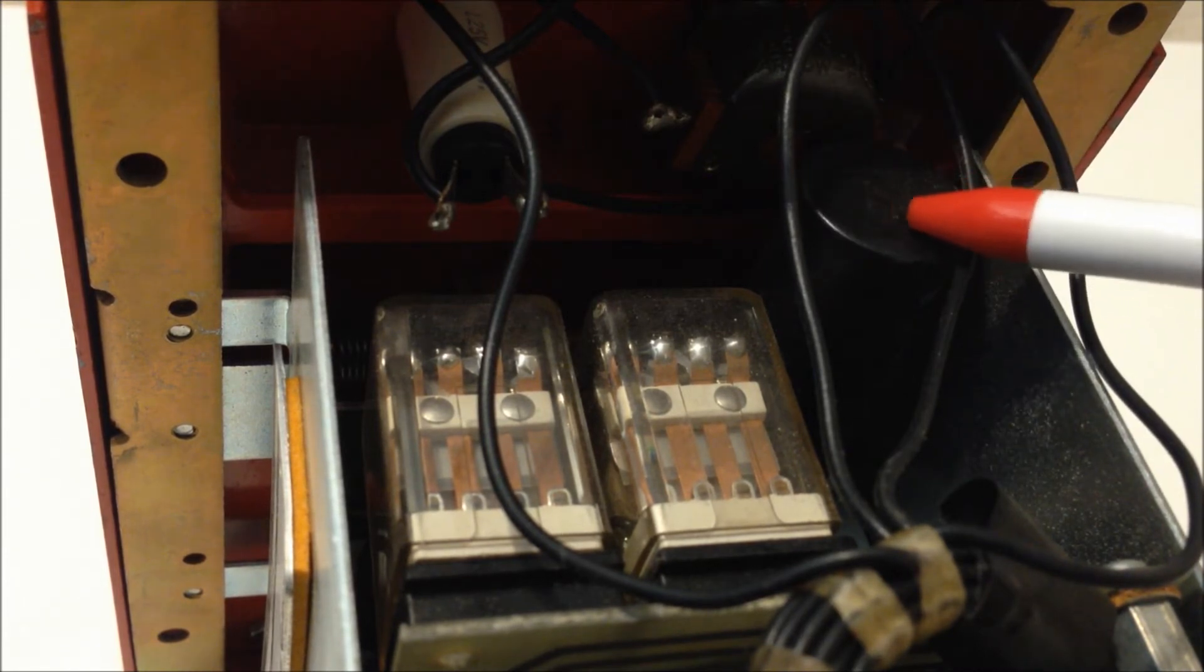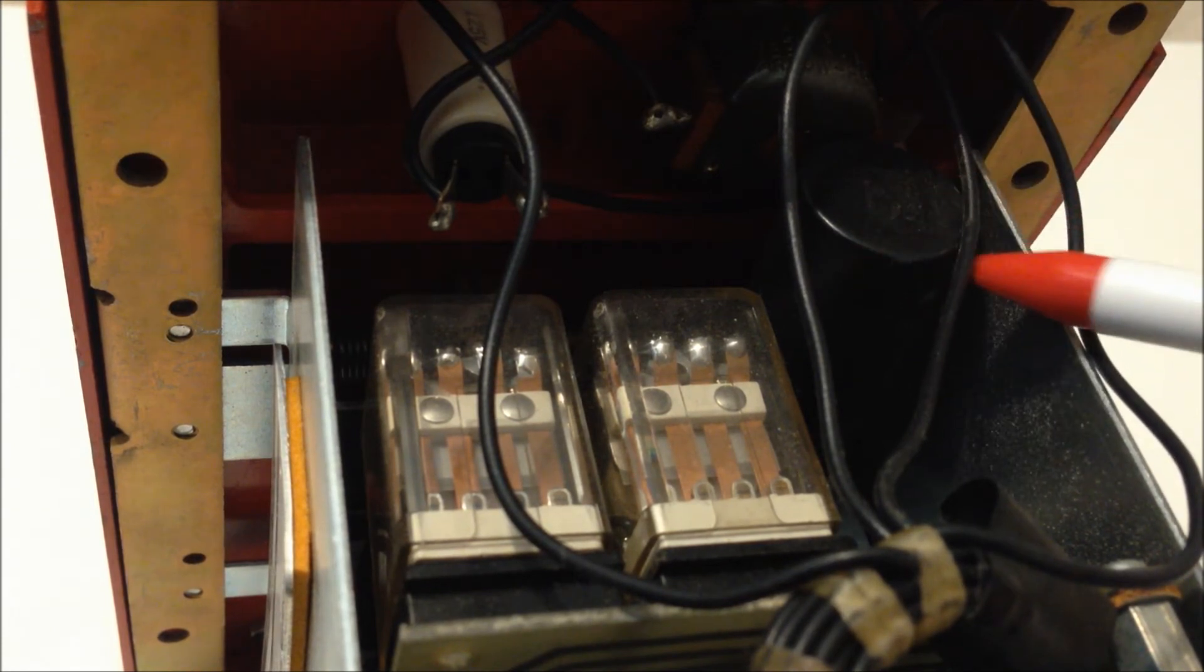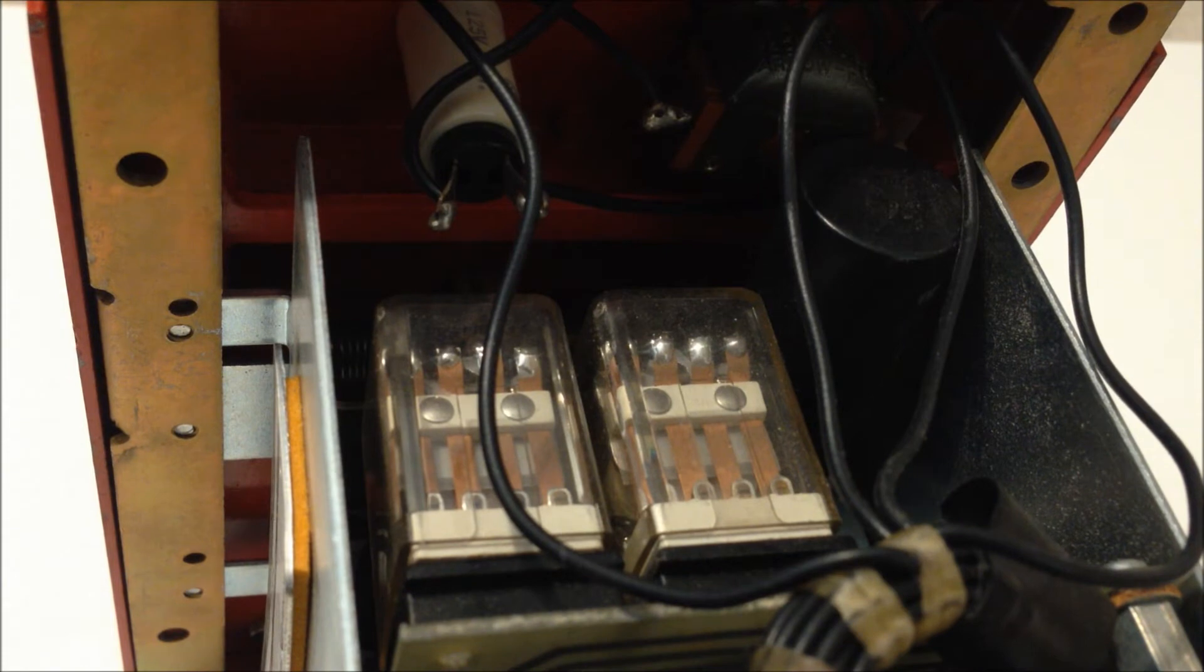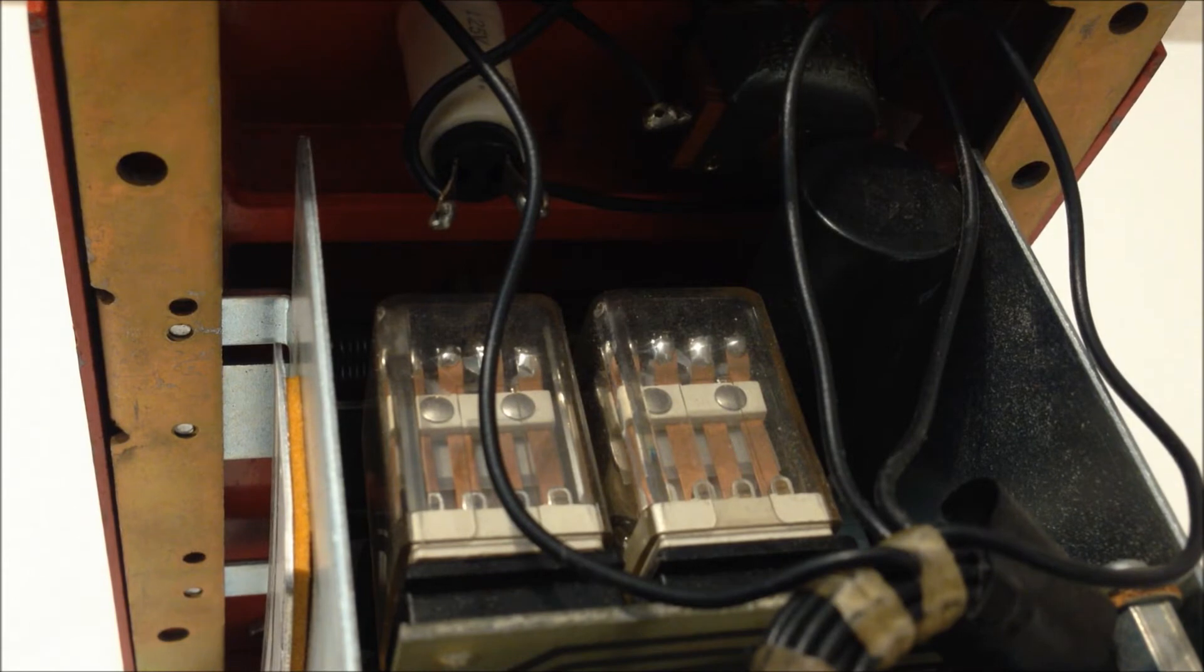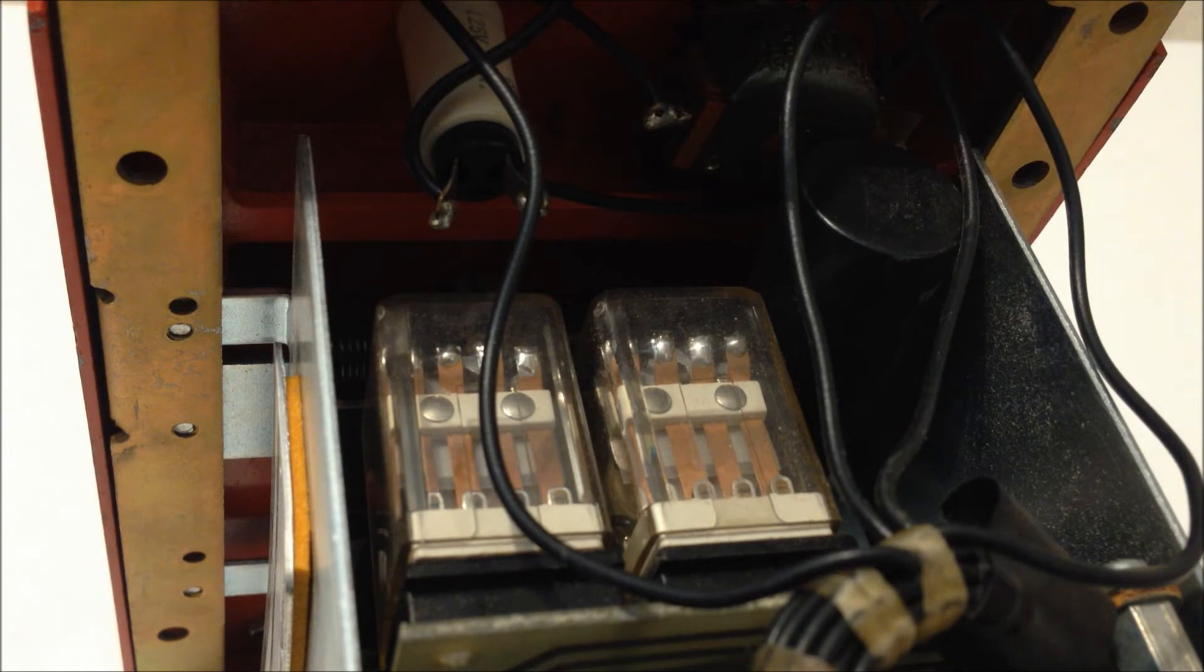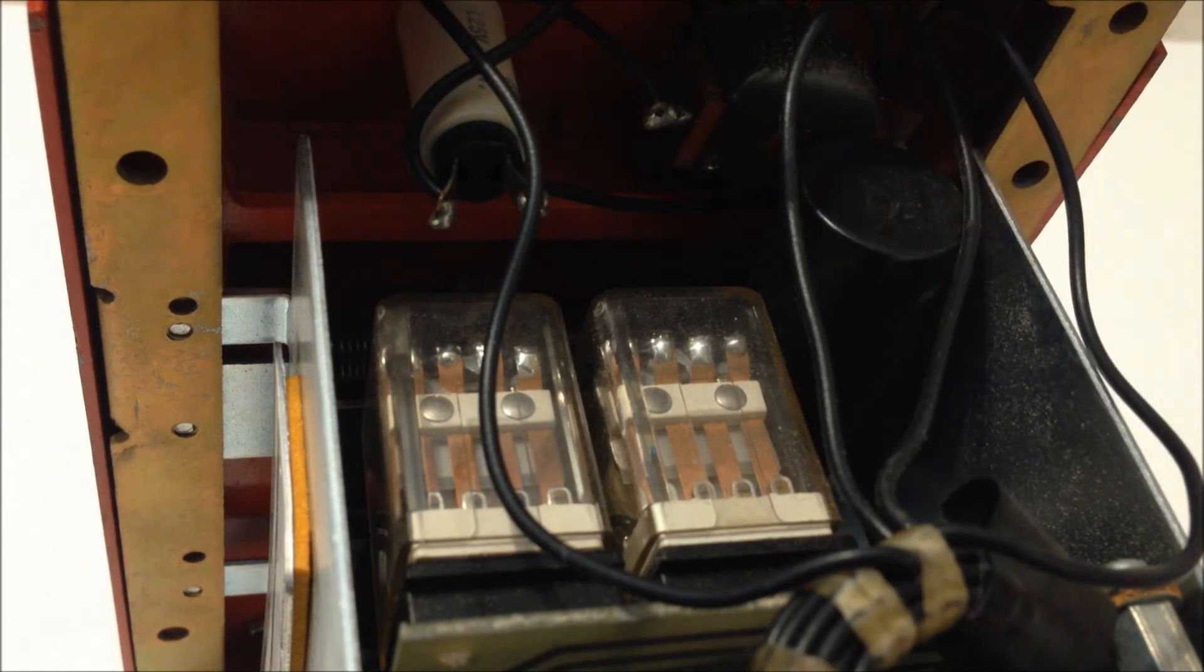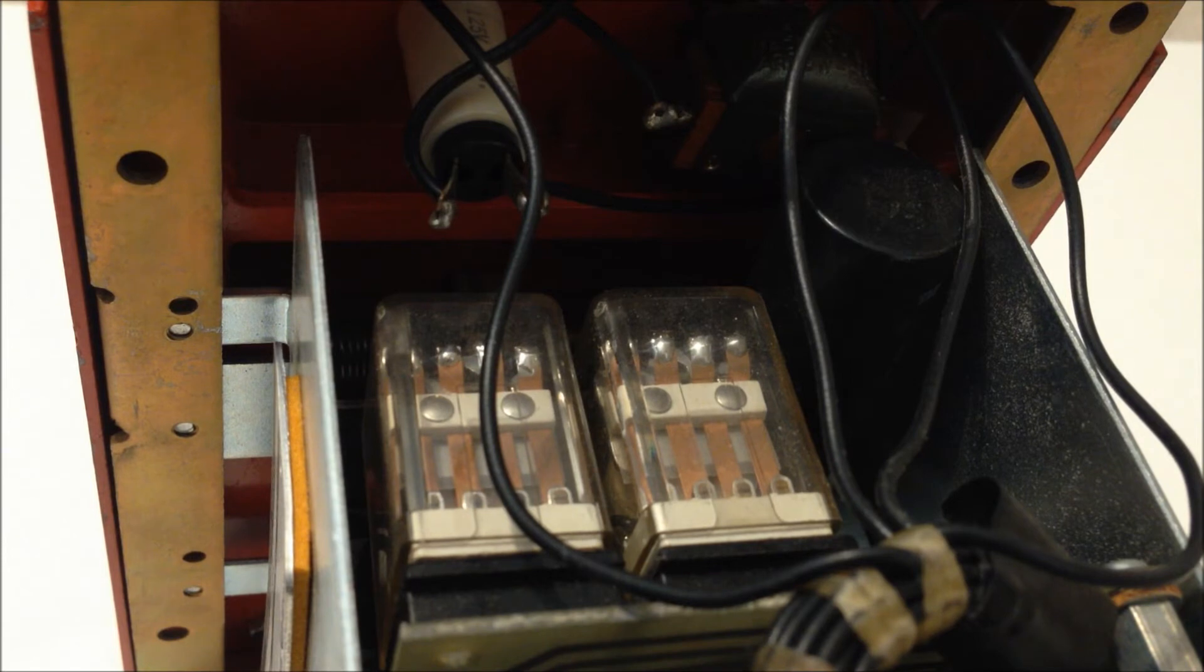Right here we have this capacitor. I can't tell if this is a starting capacitor for the motor or if it's actually a filtering capacitor for the zone that it's connected to. But I have a suspicion that it's actually a filtering capacitor because if you listen to the coding being run on horns from a wind-up pull station, it's kind of jerky and poppy and the horn won't sound perfectly clearly during the code. But from this station, the horn sounds really clear, so I'm wondering if that capacitor is actually connected in there so that it can kind of smooth out the coding from the code wheel on the micro switch, which can get a little intermittent as it sparks. Not completely a clean connection.